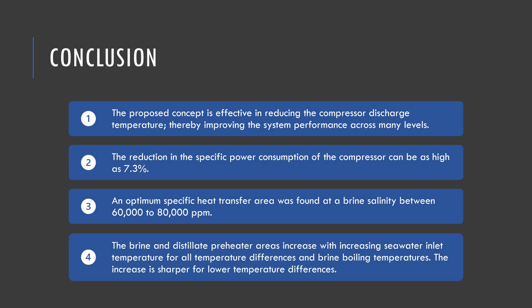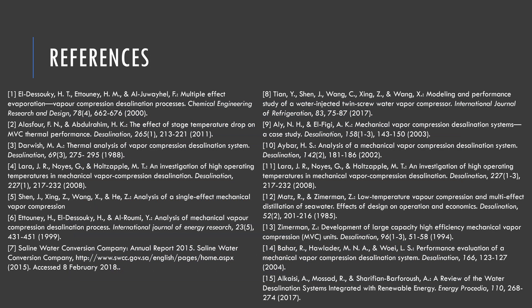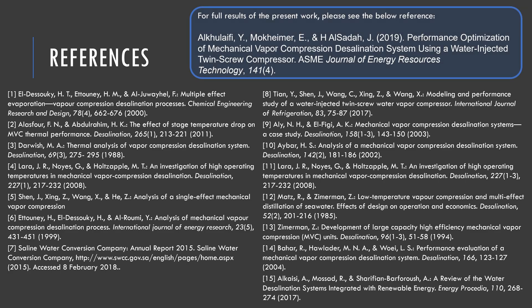To sum up, the proposed concept is effective in reducing the compressor discharge temperature, thereby improving the system performance across many levels. The reduction in specific power consumption of the compressor can be as high as 7.3 percent. An optimum specific heat transfer area exists at brine salinities between 60,000 and 80,000 parts per million. Finally, the brine and distillate preheater areas increased with increasing seawater inlet temperature for all temperature lifts and brine boiling temperatures, with the increase being sharper for lower temperature differences. To find out more about our work, please see the reference. Thank you.